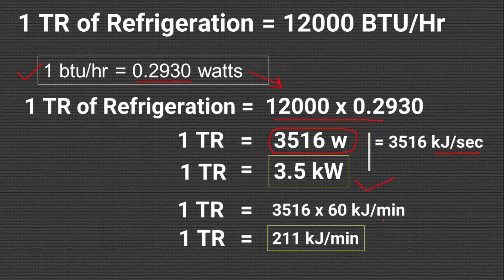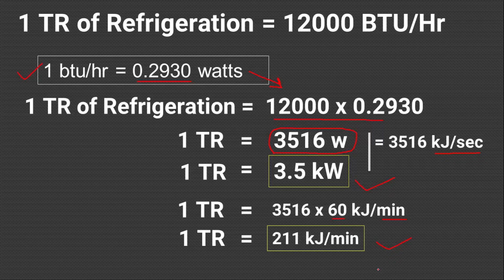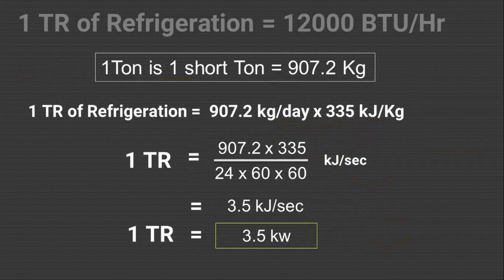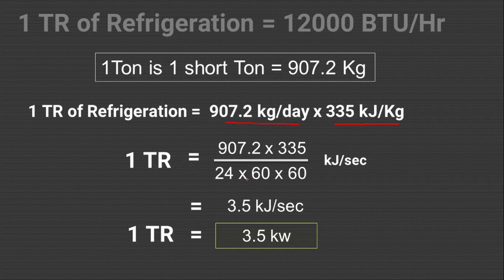To convert Kilowatts into KJ per minute, we multiply by 60, so 1TR is equal to 211 KJ per minute. Always remember, 1TR comes from 2,000 pounds or 907.2 kg of ice — it is not coming from 1,000 kg of ice. In this calculation, 1TR is 907.2 kg of ice per day multiplied by the latent heat of ice, which is 335 KJ per kg, and by calculating it we get 3.5 Kilowatts as 1TR. If by mistake you take 1,000 kg, the value becomes 3.8 Kilowatts, which is wrong. So don't confuse the units.